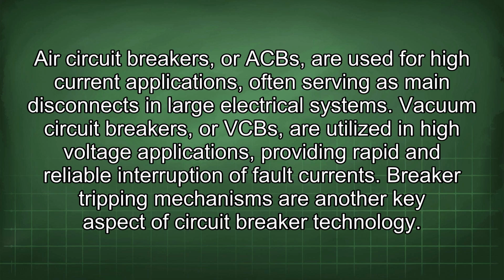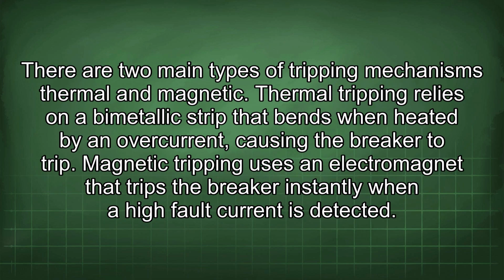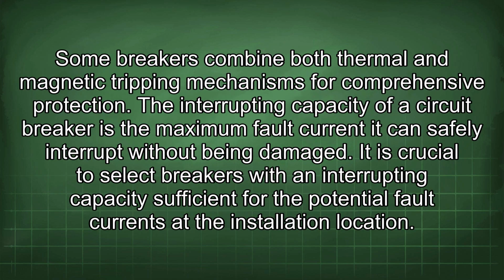Breaker tripping mechanisms are another key aspect of circuit breaker technology. There are two main types of tripping mechanisms: thermal and magnetic. Thermal tripping relies on a bimetallic strip that bends when heated by an overcurrent, causing the breaker to trip. Magnetic tripping uses an electromagnet that trips the breaker instantly when a high fault current is detected. Some breakers combine both thermal and magnetic tripping mechanisms for comprehensive protection.